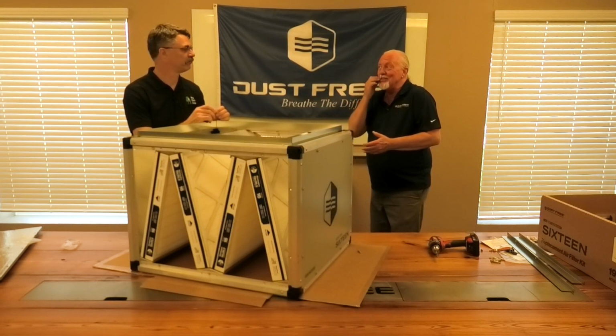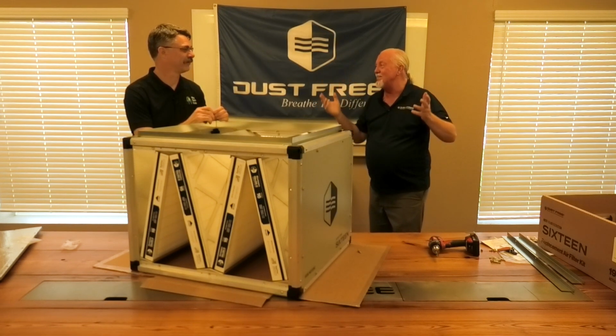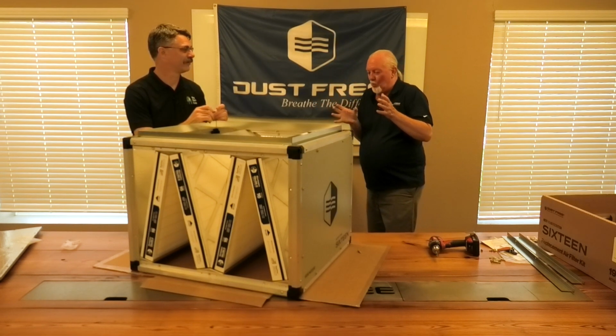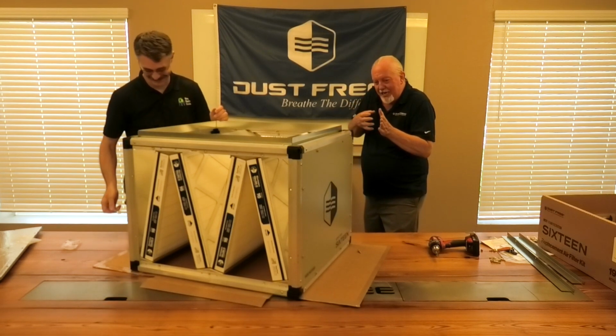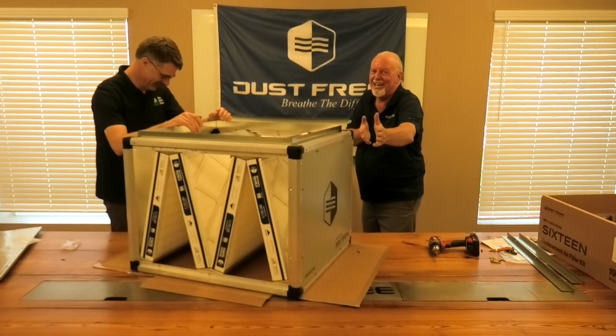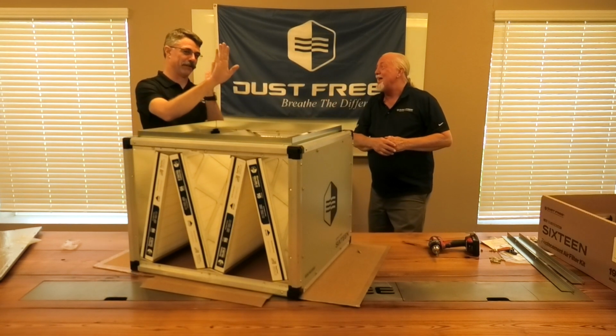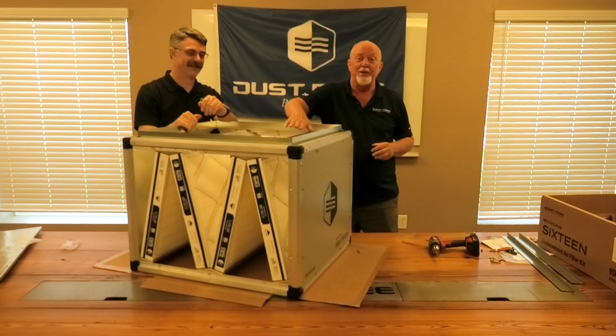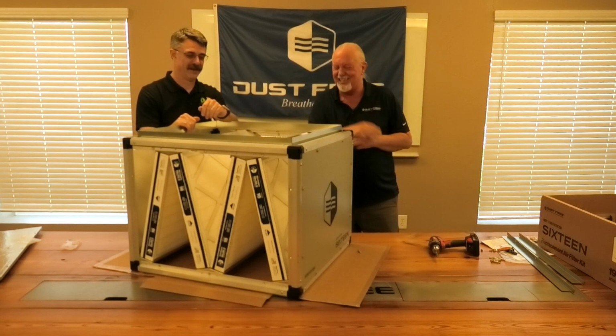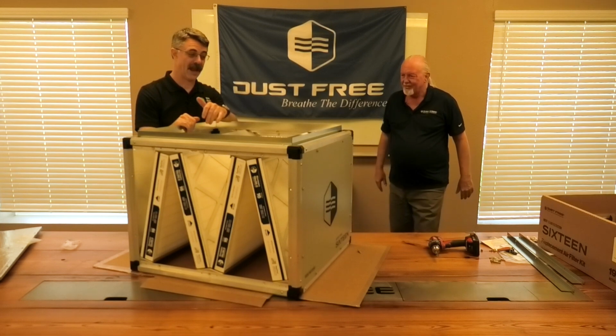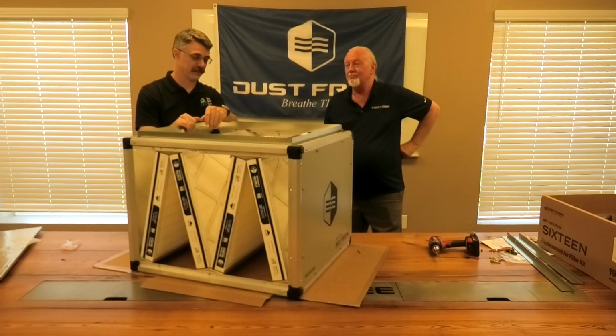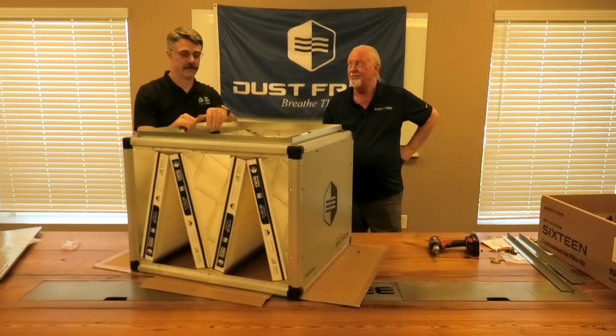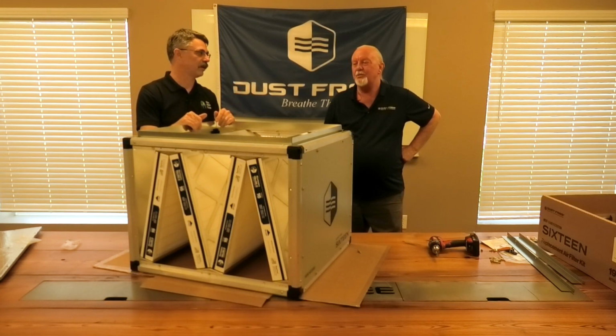I've done commercial work so many times where they hang units above T-bar ceilings, and you have to fold or roll up your filter just to slide it in and unroll it, bending the filter in half just to work it in there. There won't be any of that with this. If you bend one of these filters, you're doing something pretty good, because they're a stout filter. But if you deform that filter, you'll destroy the seal on the outside of it, it becomes compromised.